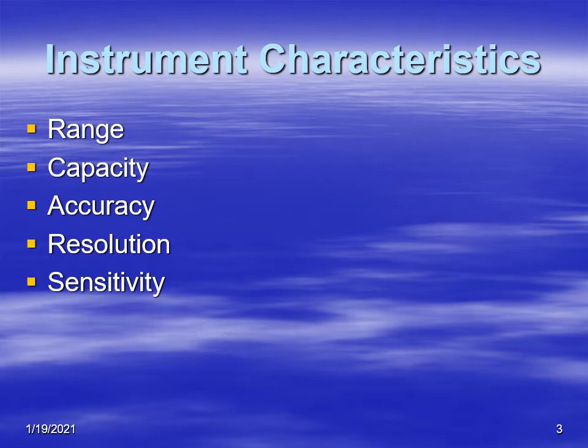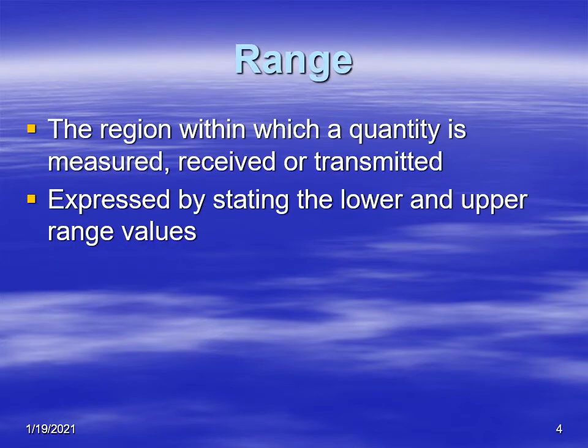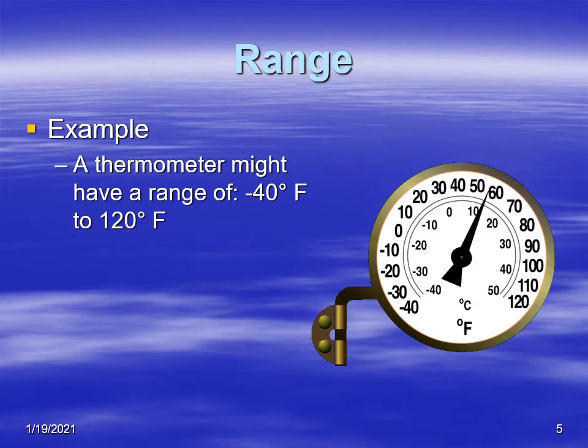We'll start out with range first. Range basically is the region in which you make your measurement, typically expressed by the top and bottom values of that instrument. An example here is a bimetal thermometer. The bimetal thermometer shows the scale going from 120 degrees Fahrenheit all the way down to minus 40, so the range is 120 down to minus 40. That's where you make your measurements.